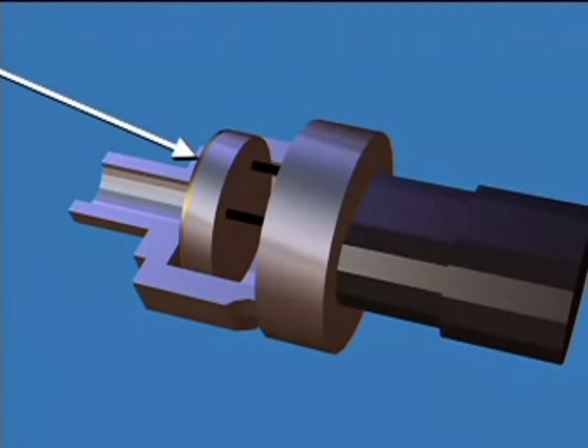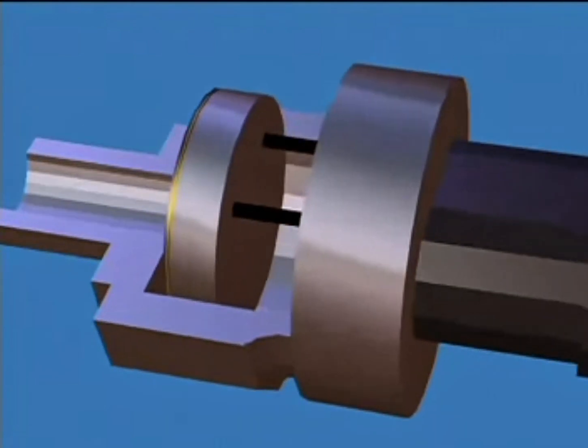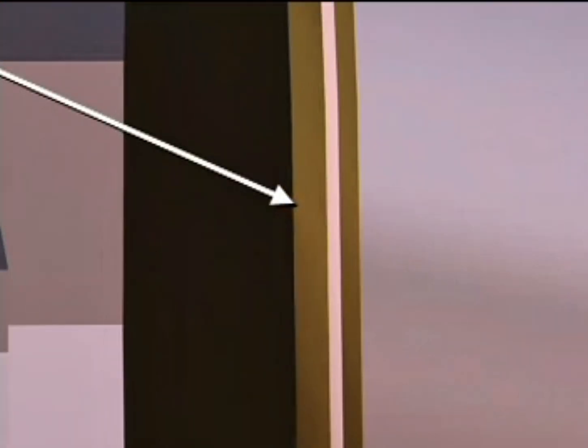Some pressure sensors work by capacitance. The pressure sensor contains a disc that has the pressure to be measured on one side and the reference pressure on the other side. Pressure acting on the disc causes it to move toward or away from a second metallic disc. As the gap changes, the capacitance also changes.